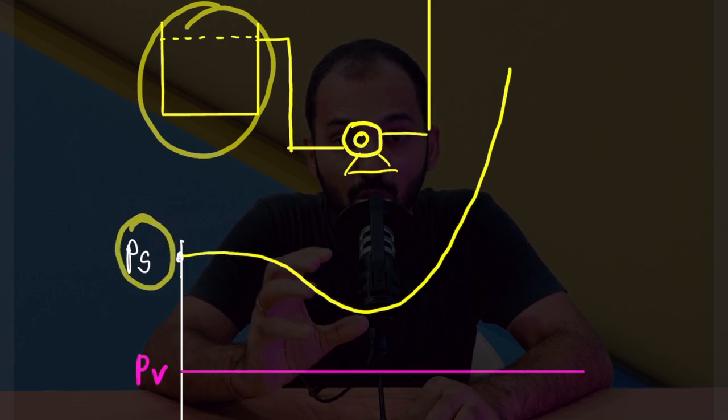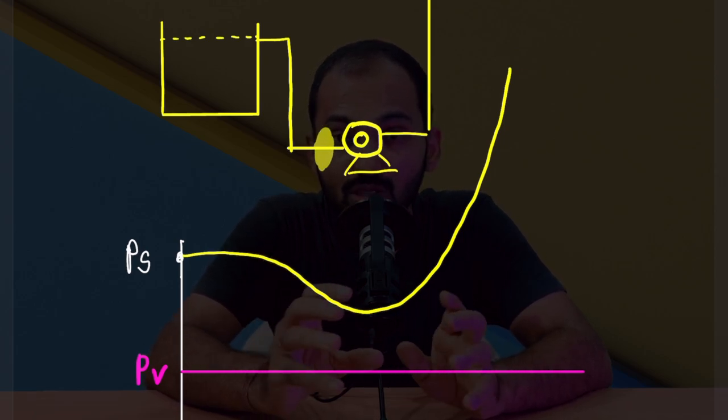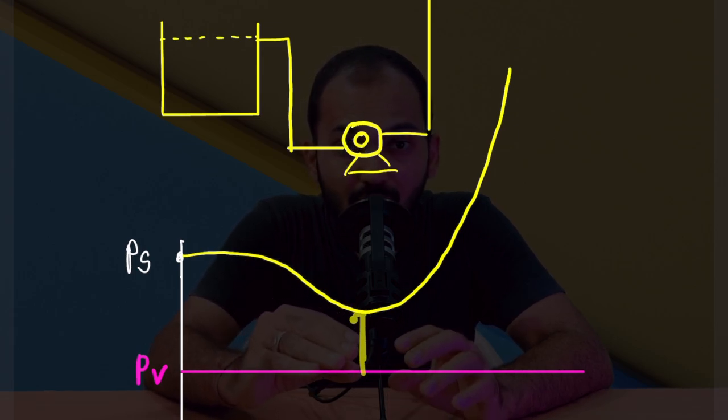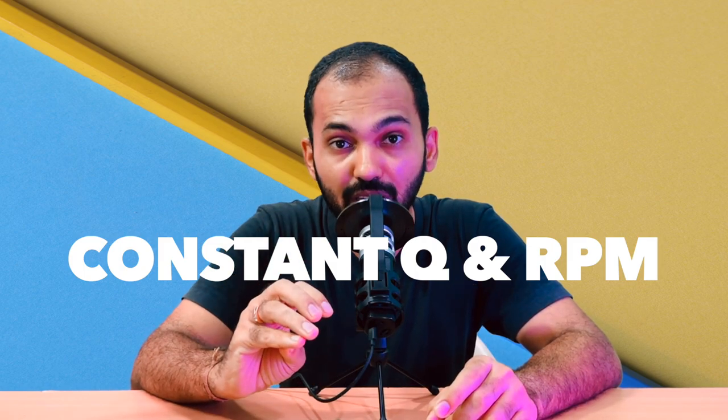From the reservoir to the impeller eye, we measure the suction pressure — the pressure as the fluid enters the pump before the impeller. The difference between suction pressure and vapor pressure, converted to head, is called NPSH available. This calculation is done at a fixed RPM and fixed flow rate. Our NPSH available = (Ps − Pv) / ρg. We need a reference value to compare against, which is given by the pump manufacturer.